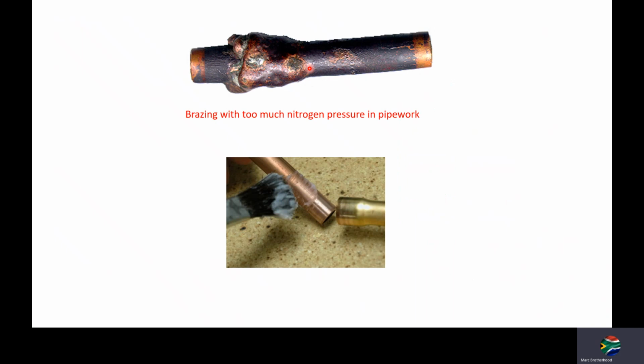On this example, there was too much nitrogen flowing in the pipework, way above atmospheric pressure. It must just be a very, very gentle puff on your hands, just slightly above atmosphere. If it's too pressurized, the nitrogen is going to bubble off all your filler material, and you're not going to get good penetration.